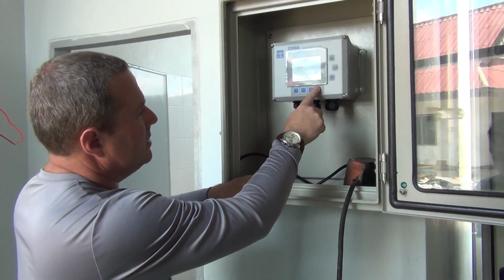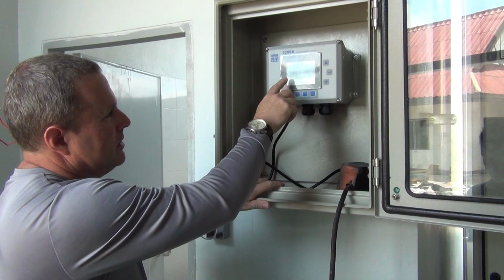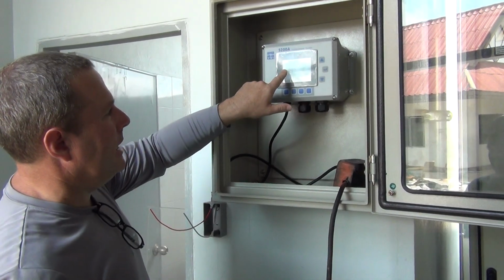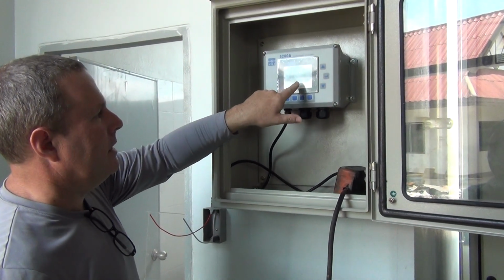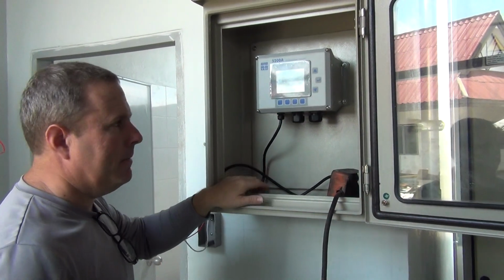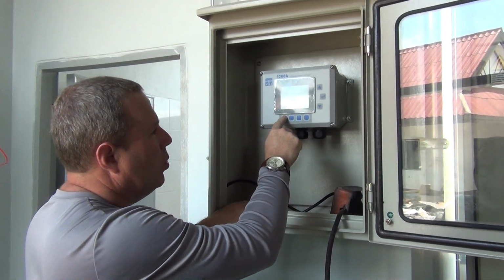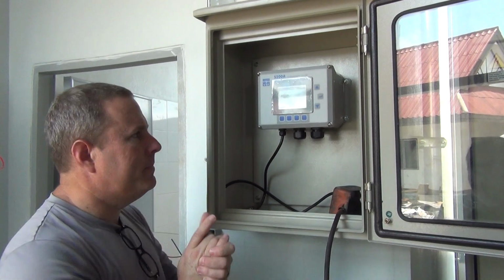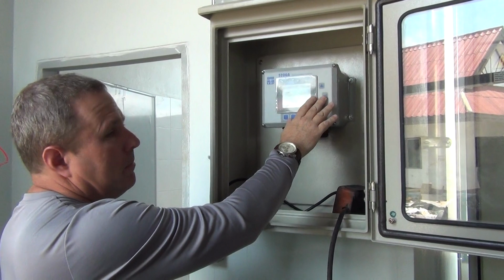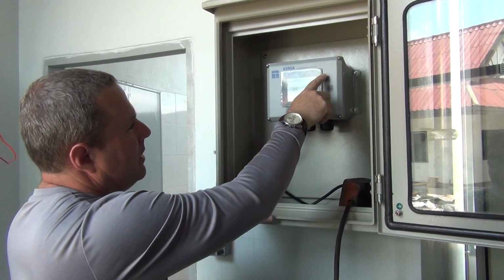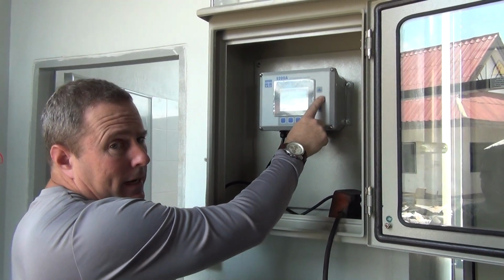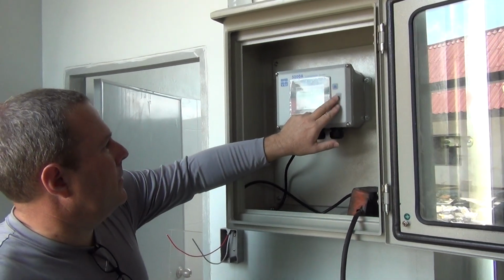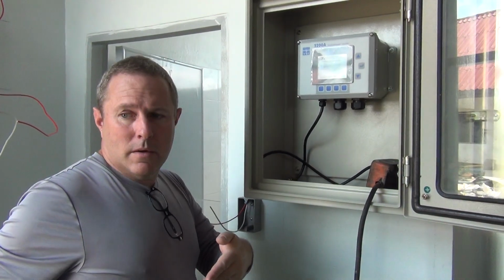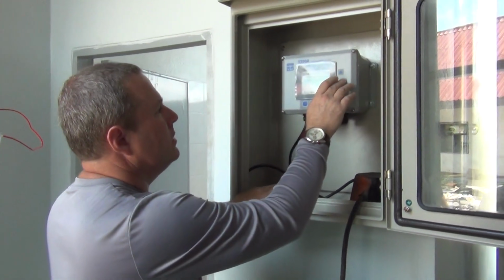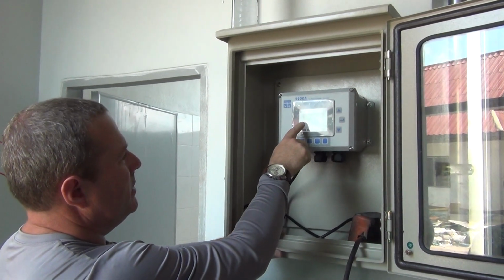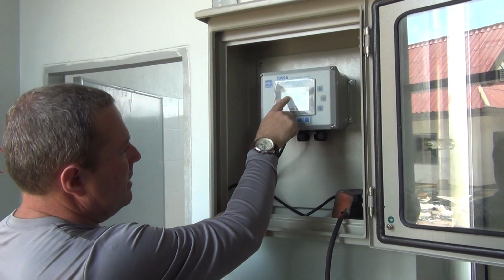So now the sensors are configured to all display. So when we put the cable and the probes on, we will have pH, ORP, temperature, conductivity, dissolved oxygen, and salinity. Okay? So the next thing is setting up what the levels to turn on and turn off. Okay? So we will go to the system menu and press enter, and we are going to set the time and date. So the format here that you use is day, month, year. Day, month, year. So I'm going to change it from the US default to be the settings here. Now I can do day, month, year 2-digit, or I can do day, month, year 4-digit.